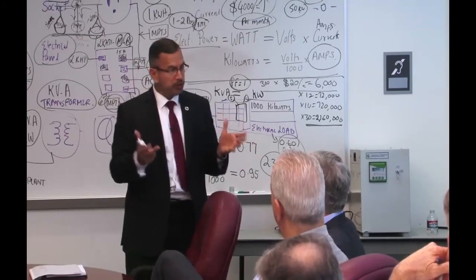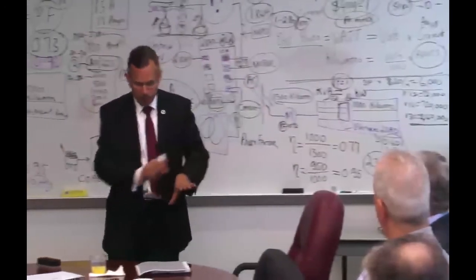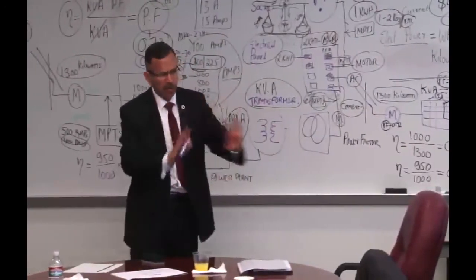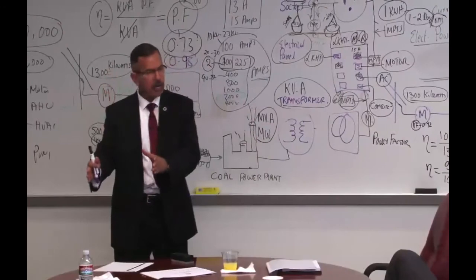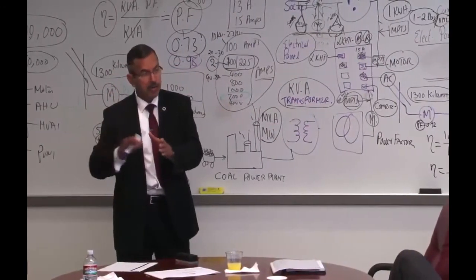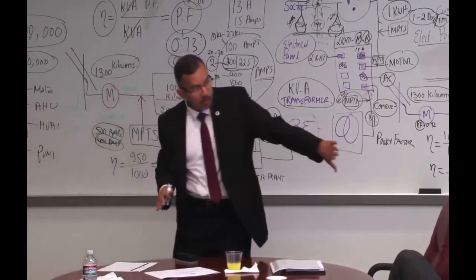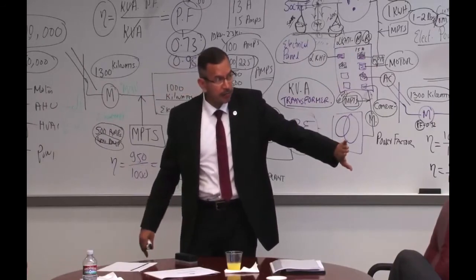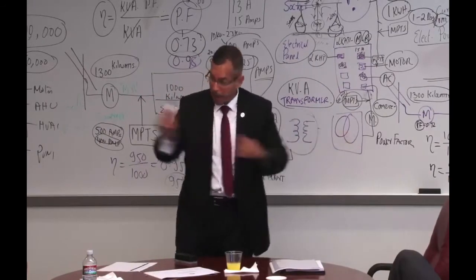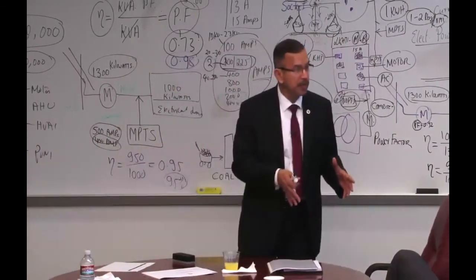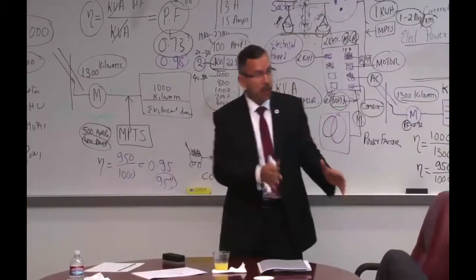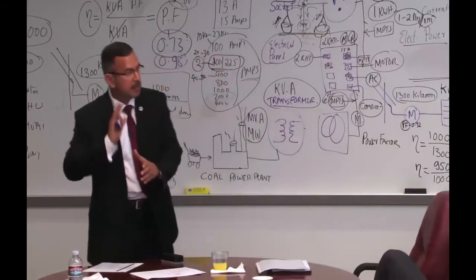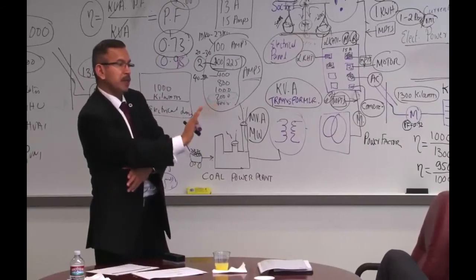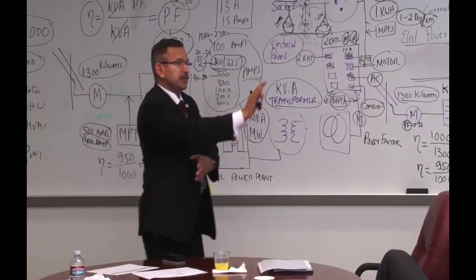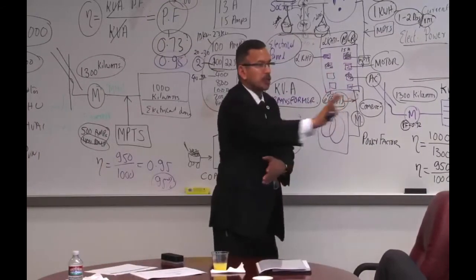So you use this in conjunction, don't change anything like you said. You already have a battery backup system, go put an MPTS. Always put the MPTS upstream of the solutions that you have. Don't let a battery feed an MPTS unit. Basic rule of thumb: always make the MPTS feed power downstream to batteries, to VFDs, to compressors, to all these loads.